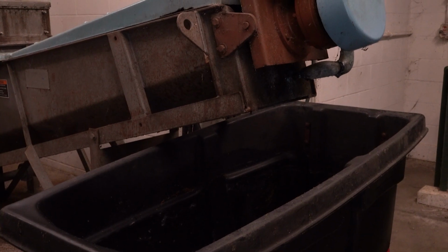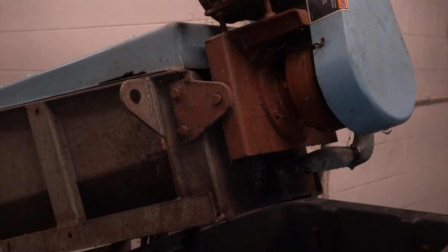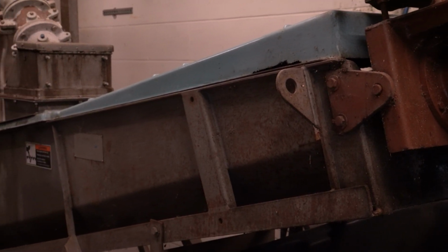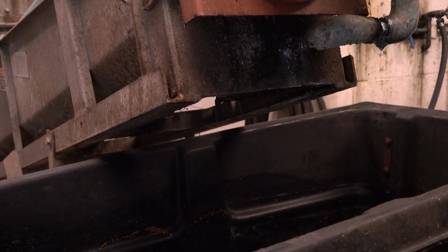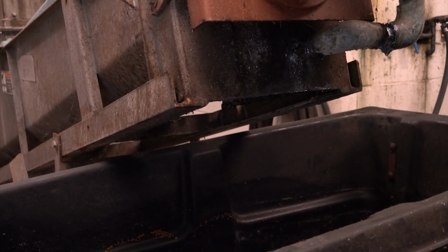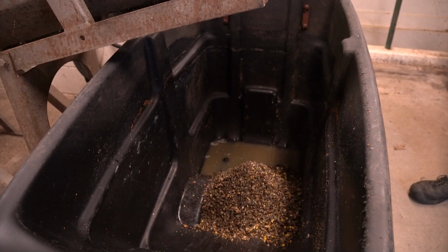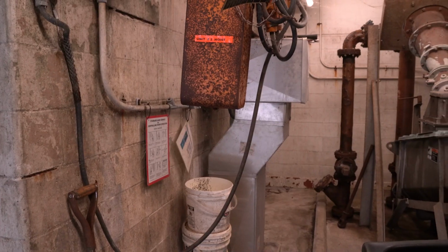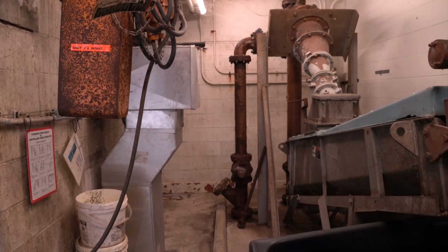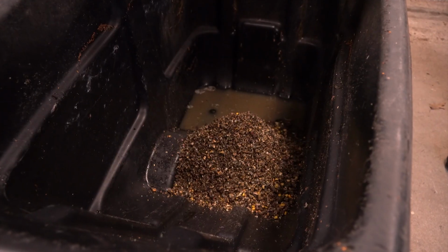Here at Harbor Station is the only place in the collection system where we are able to remove grit. As Steve mentioned earlier, Harbor Station pumps 85% of our flow to the plant. That leaves another 15% from Princess Point that pumps directly to the treatment plant. That 15% of wastewater does not receive any grit removal, which damages pumps and piping at the treatment plant. In the past 5 to 10 years, we've endured significant costs and failures due to grit.